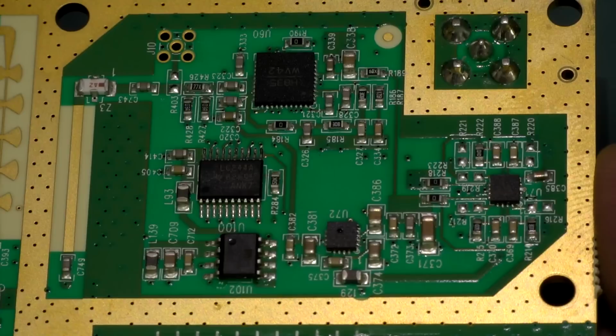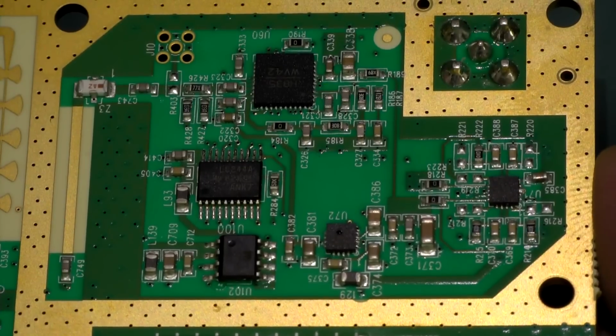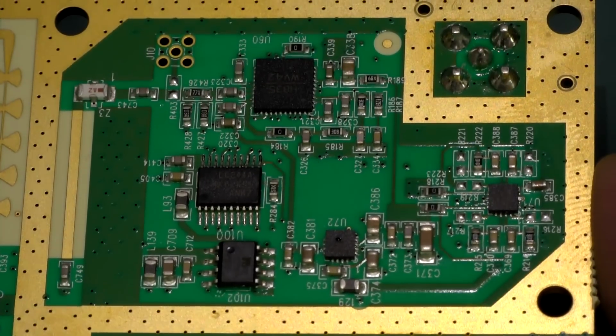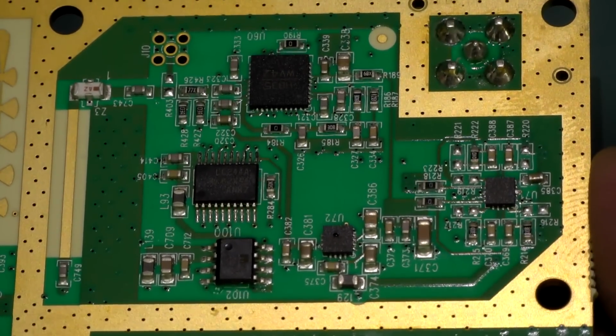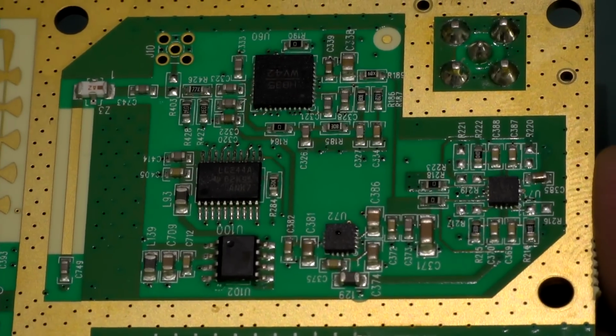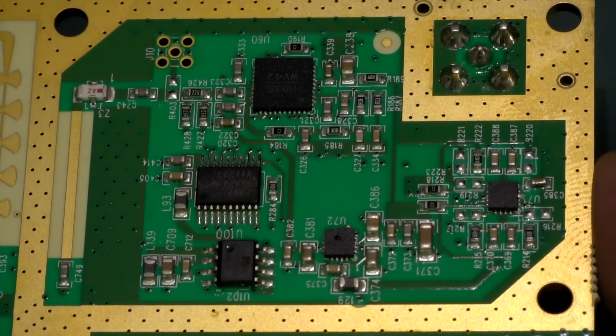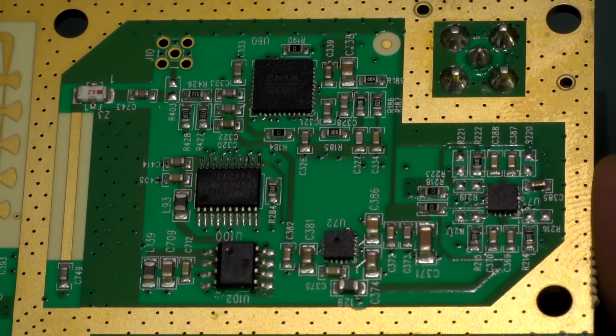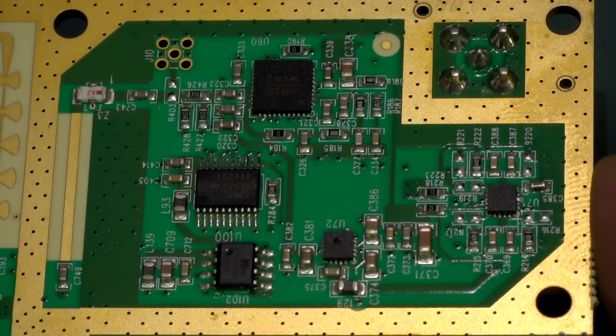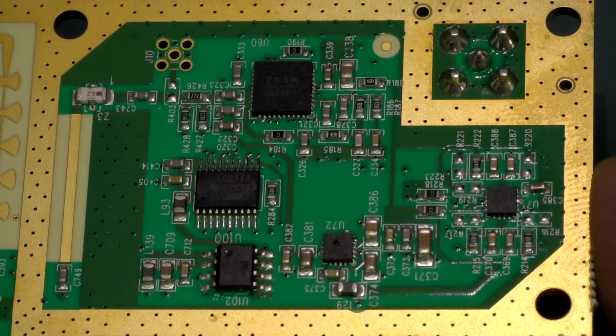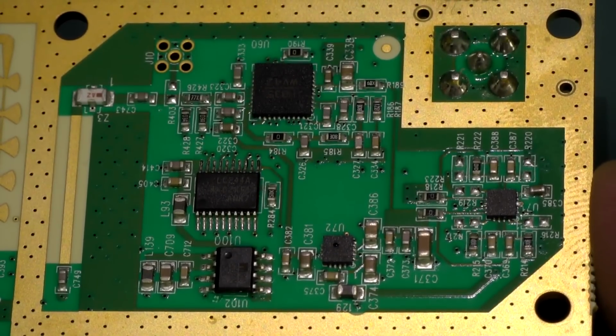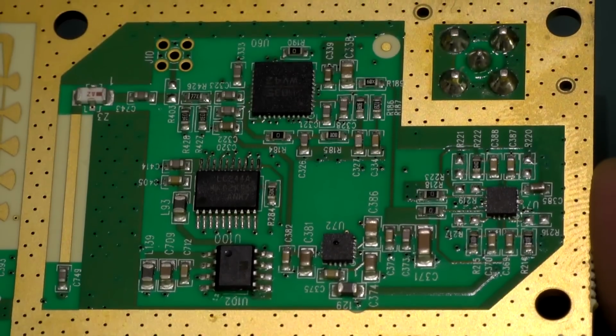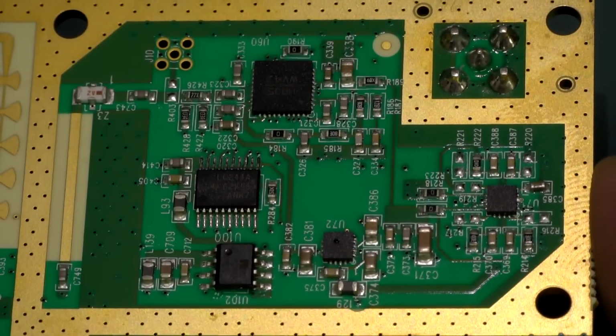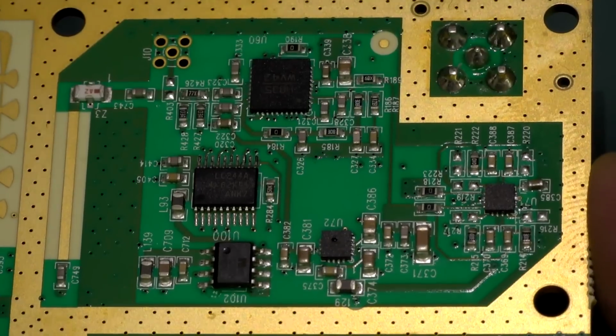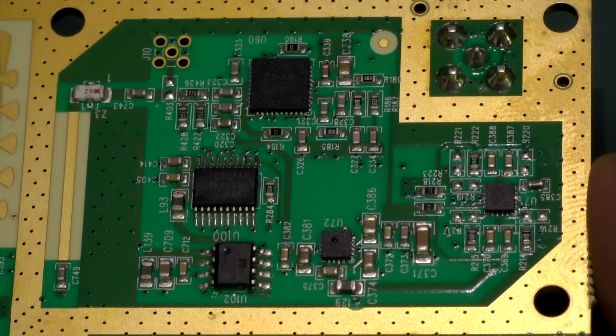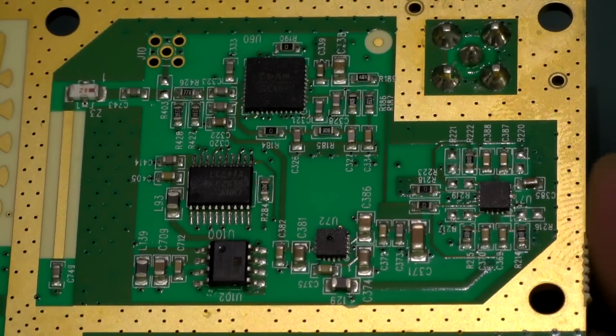Very simple. Now, of course, there's no clock on this board because the tracking generator does exactly what it says. It tracks. So it's designed to take whatever the current sweep frequency is as the Spectrum Analyzer is sweeping across from your start frequency to your stop frequency. Then this is just designed to track that. It generates the same frequency as what it's tracking. So that's why it doesn't need its own oscillator.